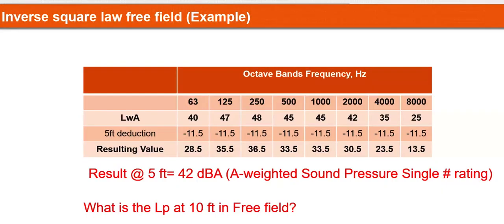All right, if you were paying attention, you get 6 decibels less per doubling of distance. That would be 36 dBA. Think about this mixed flow fan, perhaps close to a parking lot right outside of a school by a window, where the design goal inside a classroom is 35 dBA for a high learning space. Doubling the distance without using an enclosure, for example, would give you the 35 dBA when they open the window in that classroom. So the message is, use your distances to your advantage.